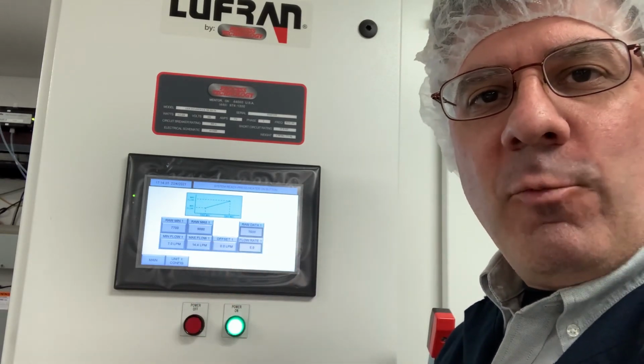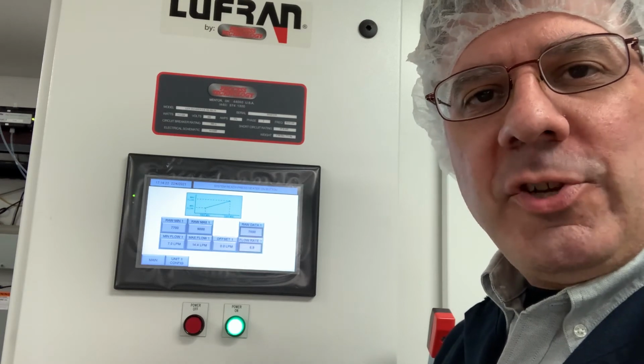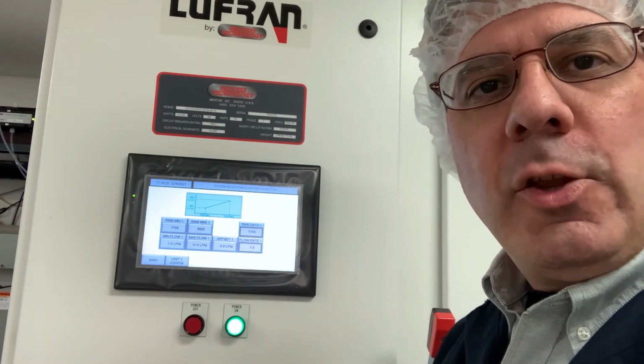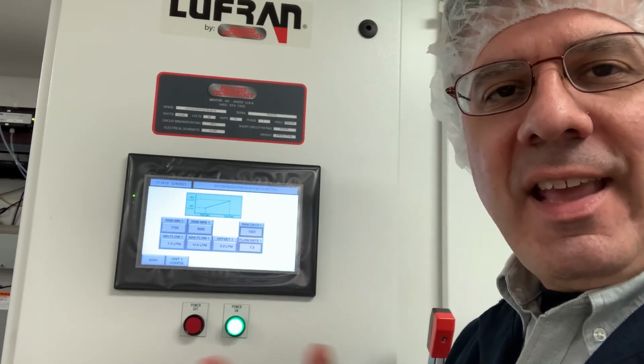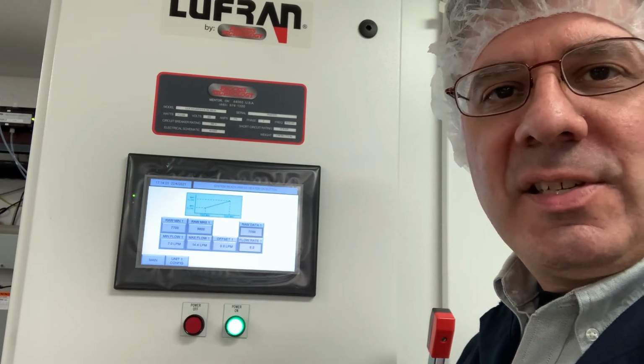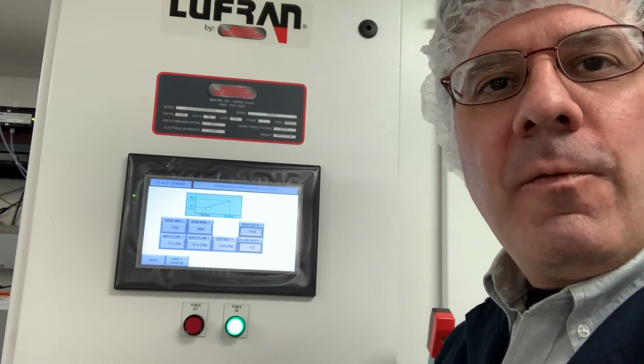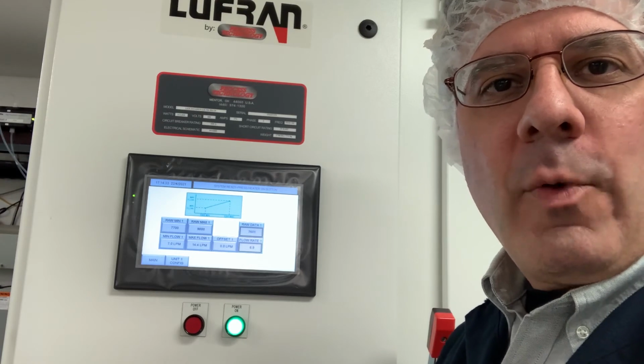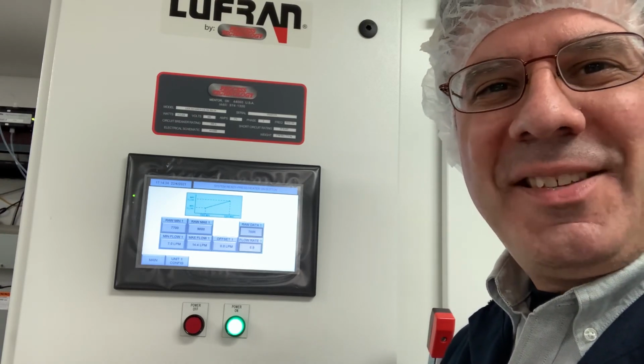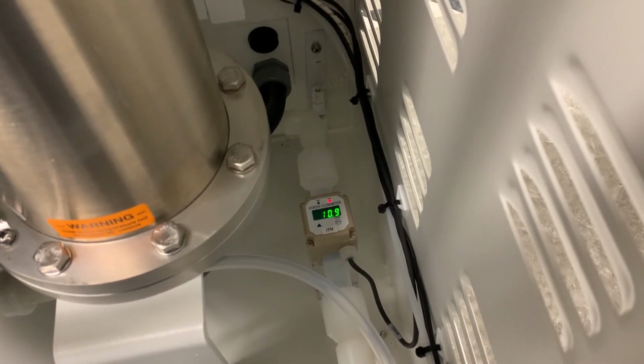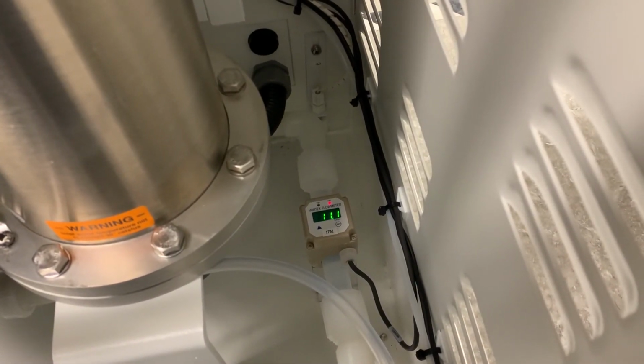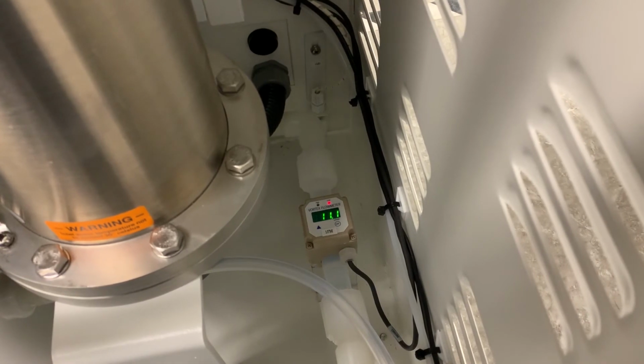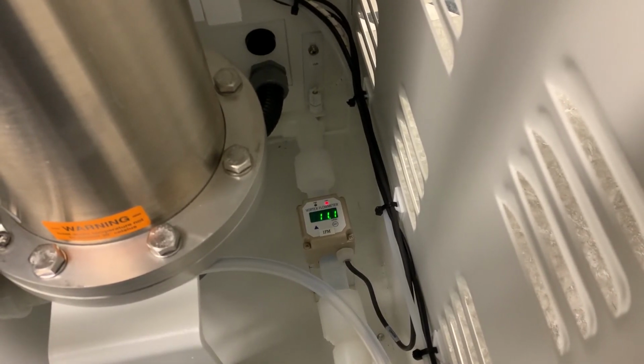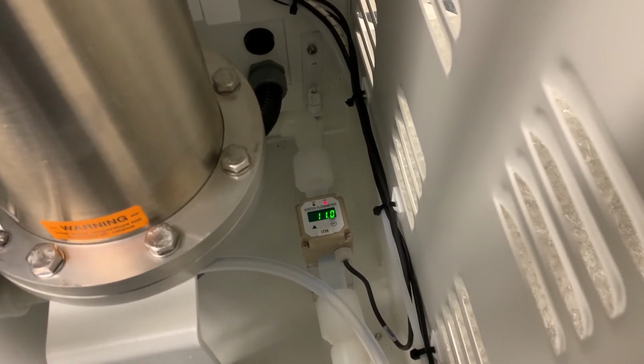For the last step, which is just a double check, we're going to adjust our flow rate for somewhere between those 2 values, and then let's see how the flow meter and this display agree with each other. For this, I'm going to try to set the flow rate for around 12 liters a minute and see if they agree. I realize that 11 liters per minute is closer to the middle, so I have adjusted your flow rate for about 11 liters a minute here. Let's see what the display says on the front.